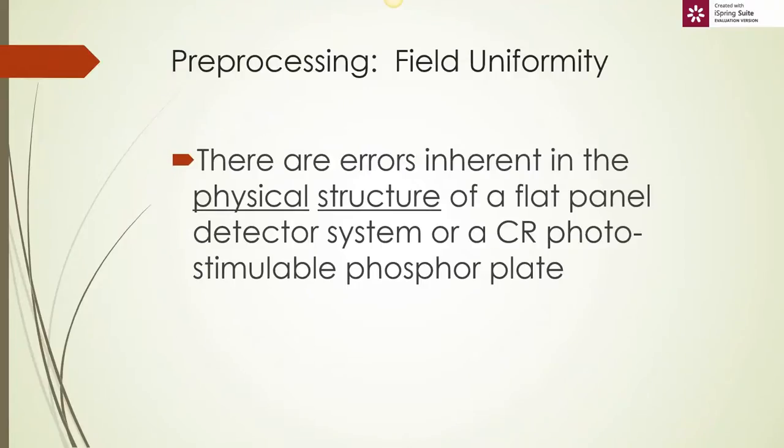Now, pre-processing, one of the things we have to keep in mind, and this doesn't matter whether we're talking about a DR flat panel detector or frankly a PSP plate, is that they are not 100% uniform. It is possible, for example, for a TFT to be dead and not sending any data at all.